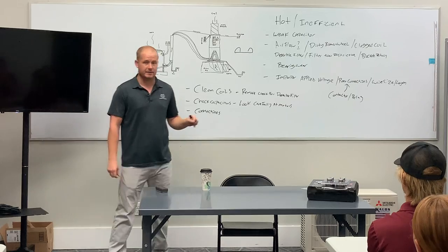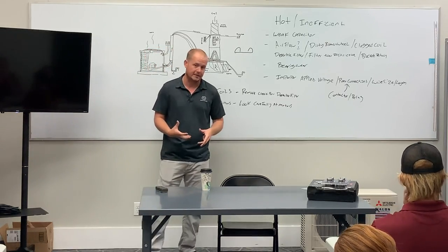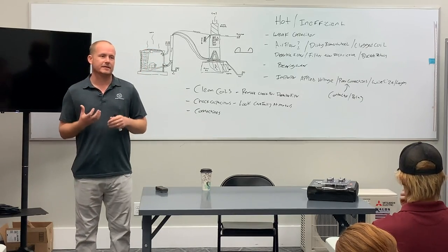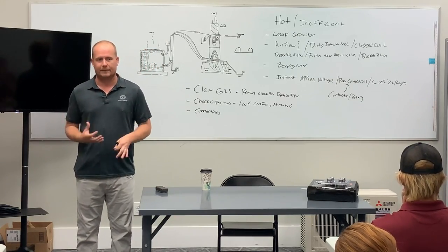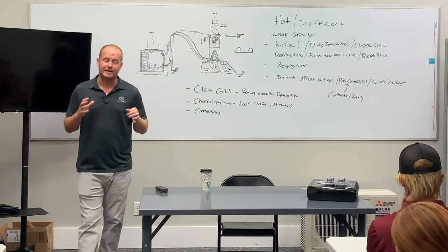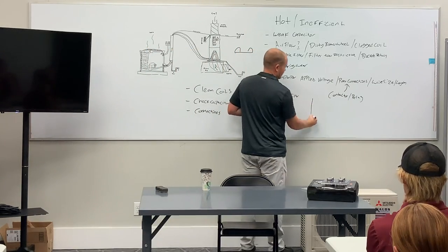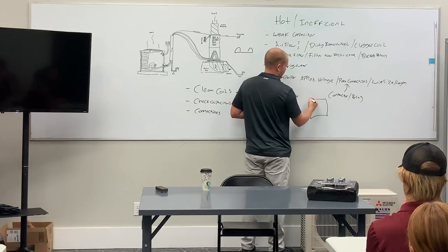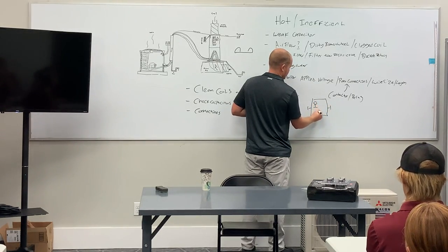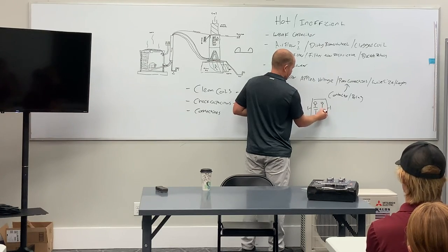We talk a lot about this. We've done a lot of demonstrations in the past about what an unacceptably pitted contactor is. What you're really looking for is voltage drop. Now, the problem is there is no trade standard on what acceptable voltage drop is across the contactor. So you can test. We're just going to pretend this is a contactor here. Put our little low voltage connections here. We'll make it a single pole contactor here.